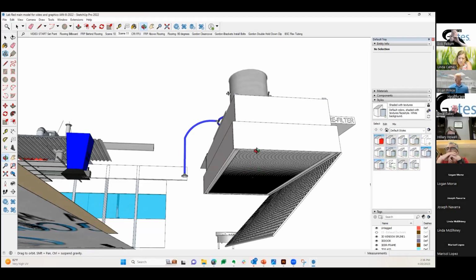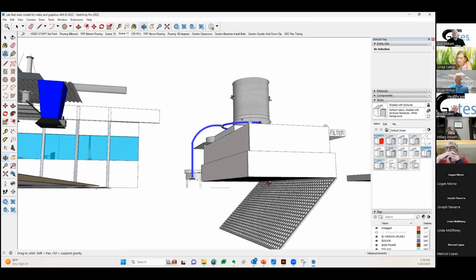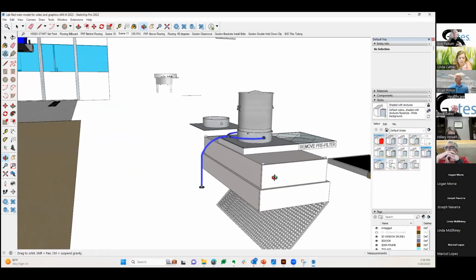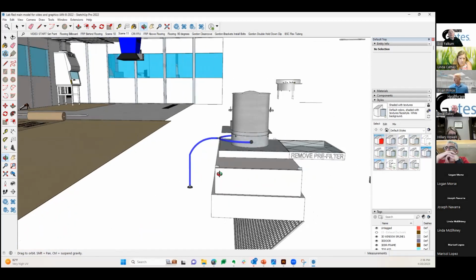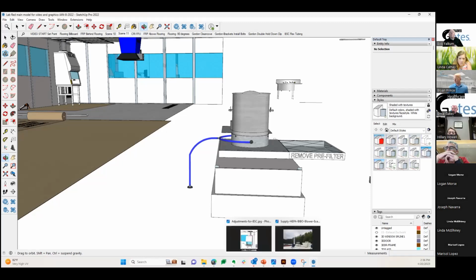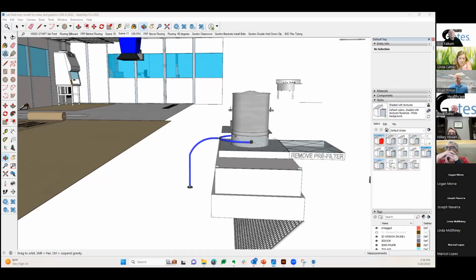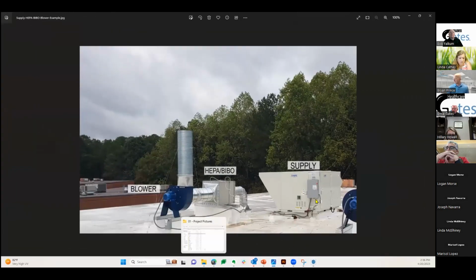I respectfully disagree with this. These units come with pre-filters, and what a stupid spot to put them, excuse my expression. They aren't good enough to take care of the return air from the room anyhow. The air coming in from outside, your makeup air, that's where you need good filtration. If you do that, you're good. So yes, please remove the pre-filter.